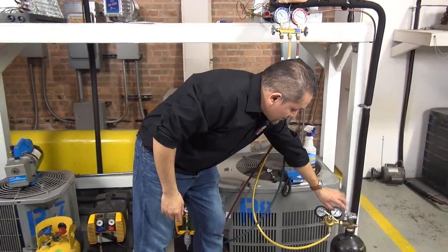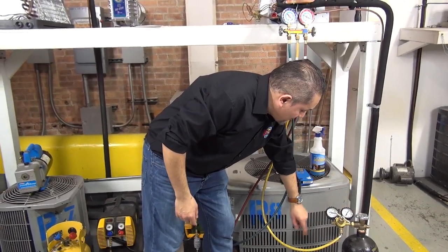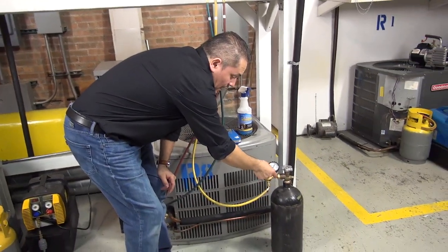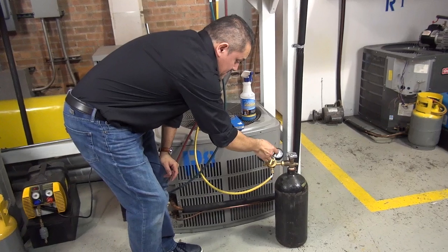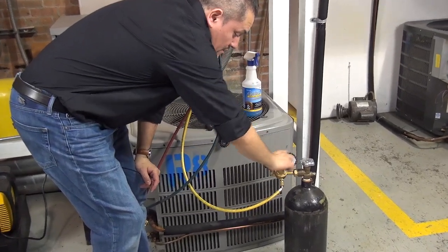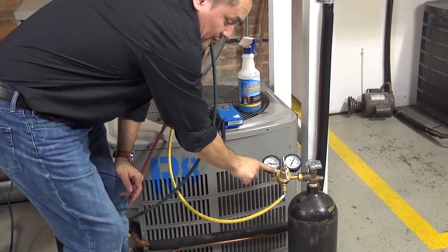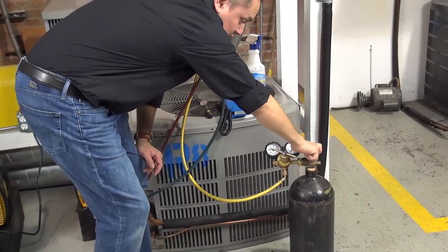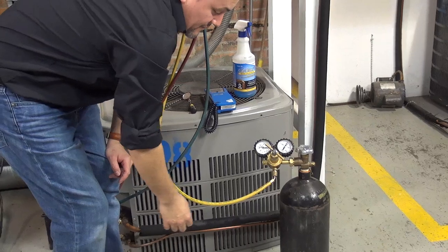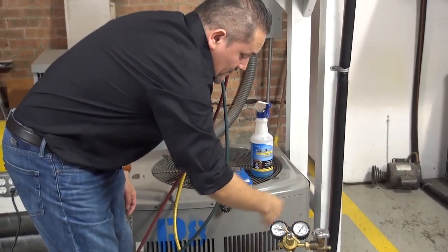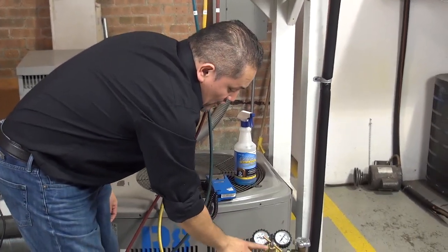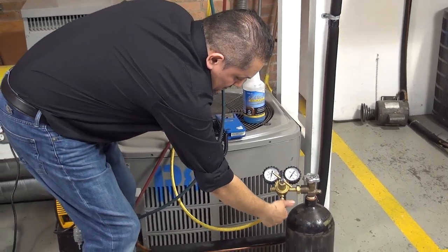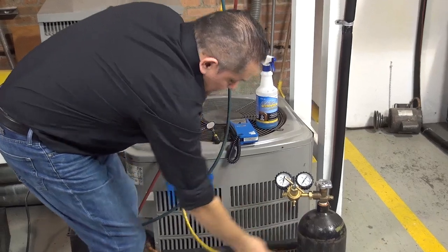My high side pressure on the tank is 2000 psi, no problem. What you're gonna have to do is turn the regulator counterclockwise, just to make sure to release the pressure from the regulator, and also you're gonna make sure you close the main valve of the tank. Once you turn this regulator counterclockwise, there should be no more pressure coming out, maybe a little bit of nitrogen, and now you can take off the hose, just like that.